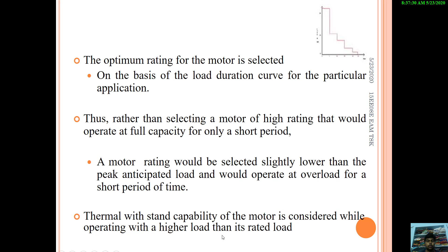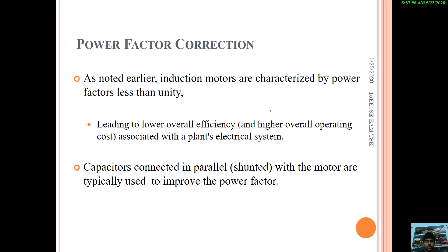The next factor is power factor correction. As noted earlier, induction motors are characterized by a power factor less than unity, which leads to lower overall efficiency and decreases the power factor associated with the plant's electrical system. In order to avoid this, capacitors are connected in parallel with the motor, which are typically used to improve the power factor.